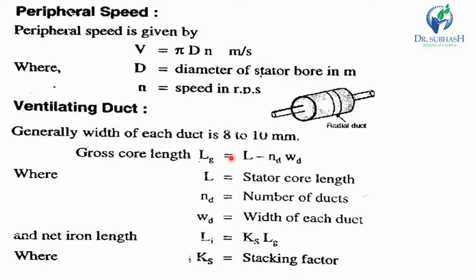If we use a special construction, then a higher peripheral speed like 45 meter per second we allow. But if we choose a higher value of speed for a special machine, the cost is increased. And in some normal designs, the diameter should be chosen such that the peripheral speed does not exceed 30 meter per second.